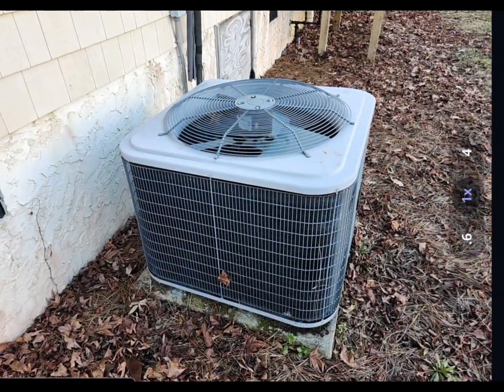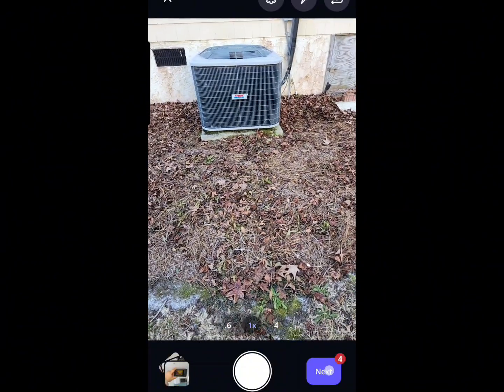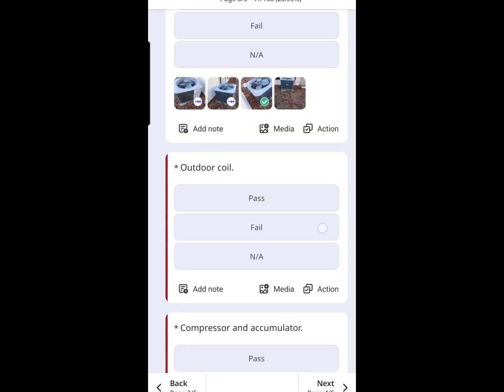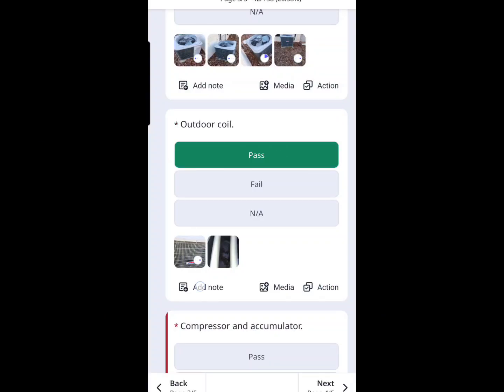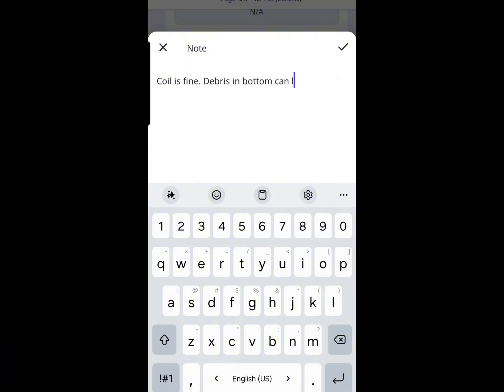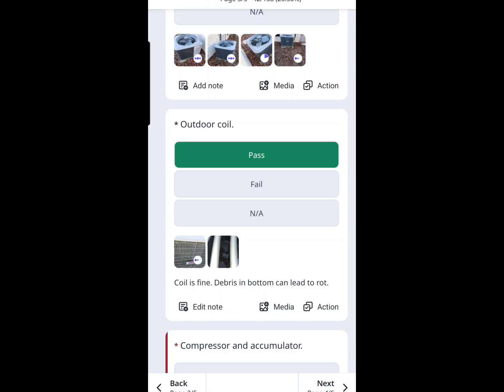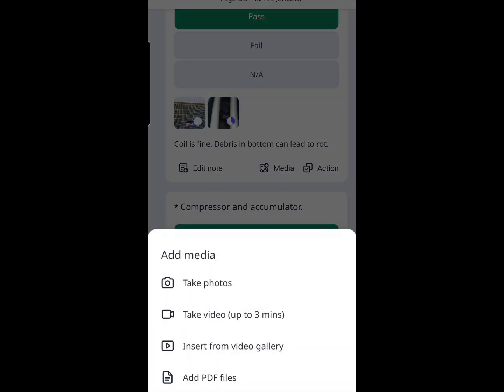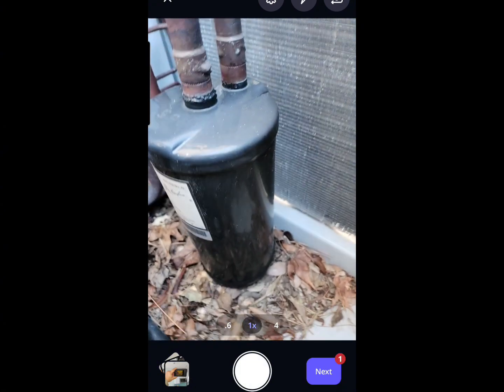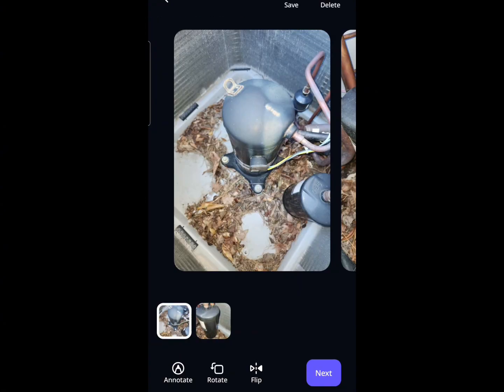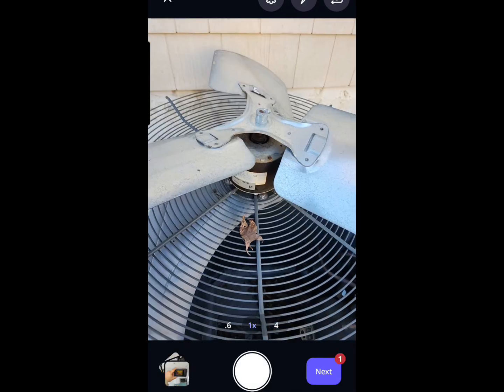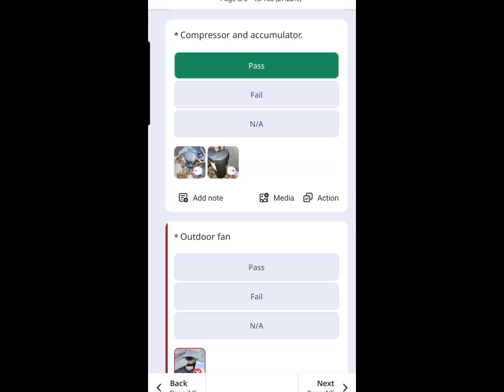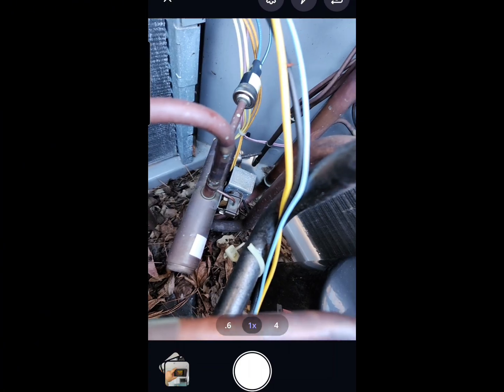For outdoor unit serviceability and workmanship, I'm looking for things like: is it level, was it installed correctly, is it in good condition, and is it easy to work on? We grab photos and it gets a pass. Then we zoom into the outdoor coil — is it clean, in good shape, corroded? More photo documentation. In this case the coil was clean, but there was a lot of debris in the bottom of the unit — looks like this unit needs some maintenance. We move on to other components like the compressor and accumulator. Obviously we have an issue with the compressor and outdoor fan motor not running, so we don't know their true condition.